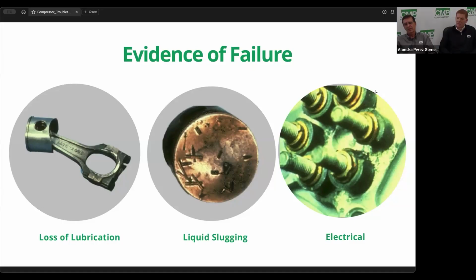You know, when I do seminars, sometimes I feel like people are going to say, "Oh Lord, he's going to talk about superheat." But 90% of all compressors fail because something in the system causes that compressor to fail. Yep. And if you don't find out what caused that compressor to fail, what you don't realize is everybody's time was wasted, from the guy that tore the compressor down, to the one who rebuilt the compressor, to the truck driver that delivered it, to you putting it in.